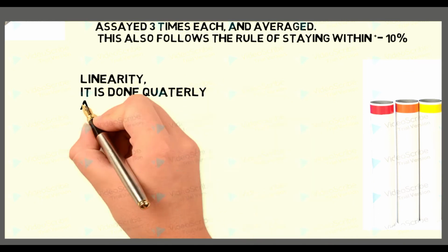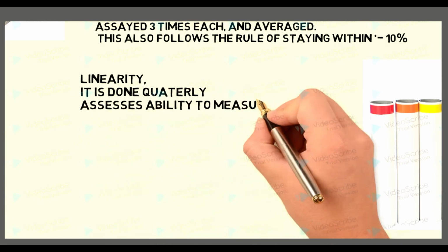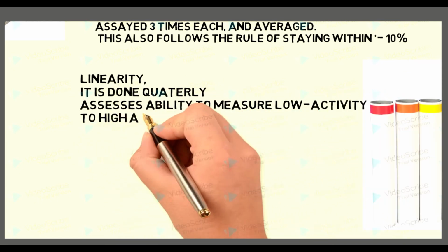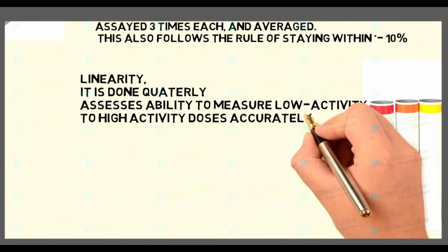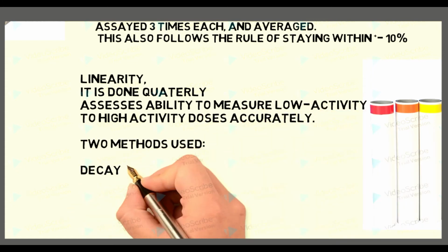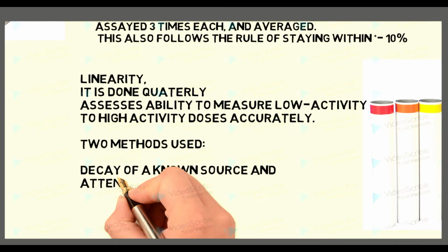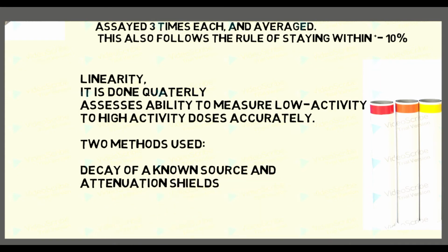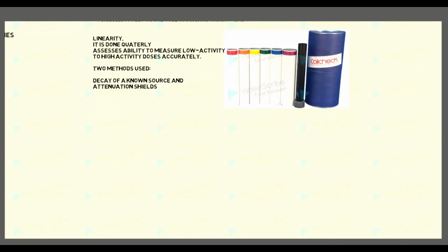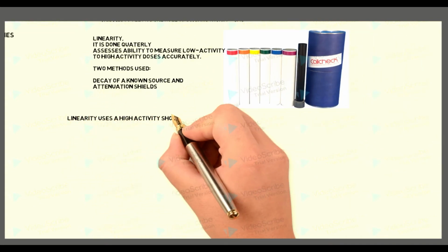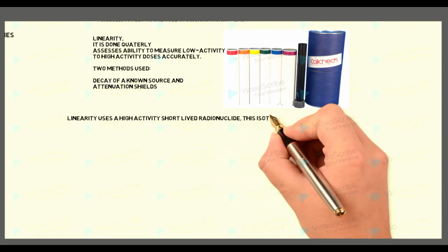Linearity. It is done quarterly, and it assesses the ability to measure low activity to high activity doses accurately. 2 methods used are decay of a known source and the attenuation shields method. Linearity uses a high-activity, short-lived radionuclide.